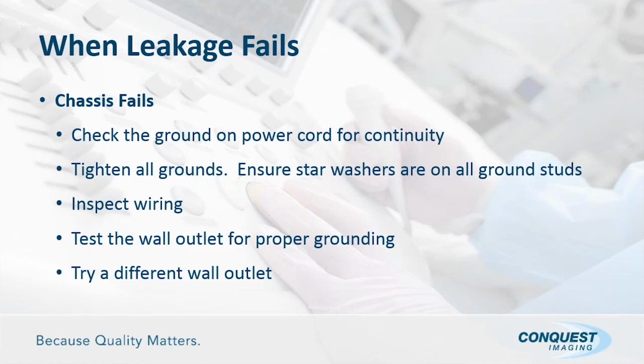But if at this point your chassis system leakage is still too high, you may want to manually disconnect the cord from the system and do another continuity check on the wires, to make sure that it's not only the ground wire that may be damaged, but maybe one of the other wires, the hot or neutral, could be damaged also. So make sure you check that as a possibility, because your power cord can cause unusual conditions as far as electrical leakage is concerned.